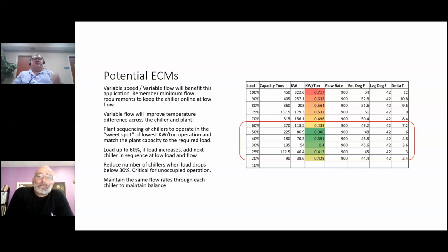I've got to do something to get this dialed into where that chiller is most efficient and improve the delta T. The only way I can do that is to vary that flow to get the delta T different. I slow the water down going through the machine. It has an easier time getting 10 degrees across it. That's right. So then I get it dialed into this lowest kW per ton. I've proven this, I think, that it is a lower kW per ton at lower flow, but a better delta T, both of which are great.